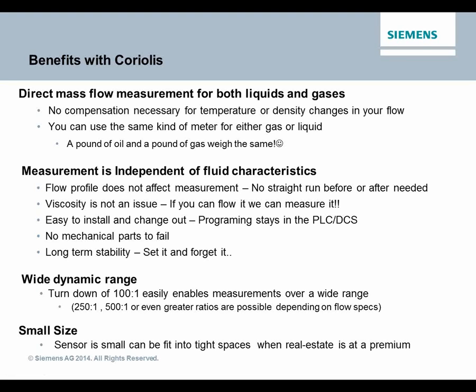You don't need any straight runs. Okay, viscosity is not a problem. If you can push 4 million centipoise fluid through your meter, you can measure it. It may be a pressure issue there, but of course you can do it. The meters are typically extremely easy to install, usually plug and play in PLCs, DCSs. Most of them have pulse outputs for analog or 4 to 20 if you want to use that.